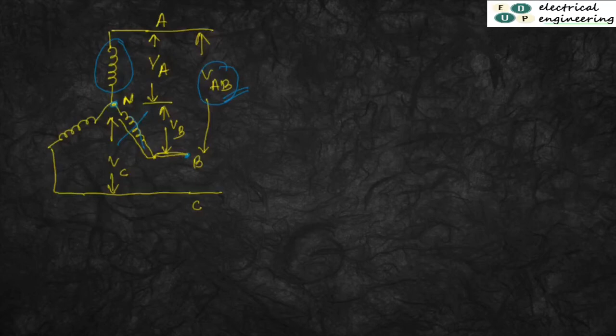That is before the fault. Now suppose after the fault this winding gets short circuited, so this point and this point are short circuited. So this total voltage will appear across this winding only. This is such a high voltage that it may damage the winding completely. So by grounding the neutral, we are making the neutral point balanced. Even after a fault, the voltage appearing across the A phase will be VA. Before the fault and after the fault, the voltage appearing across the winding will always be VA. So no issue, the load connected to the A phase will operate fine. This is another advantage of connecting the neutral to ground.